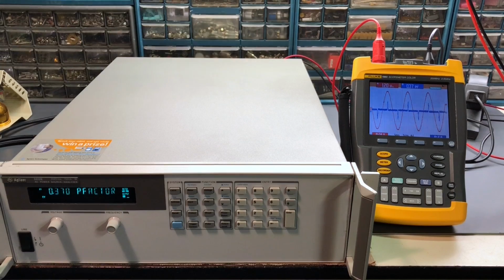So if I come up here, and I have to reach around the camera a little bit here, I'm going to increase the load on the power supply. So it's outputting just 1 amp right now, and you can see how those peaks are much larger now on the current waveform. The power factor has improved a little bit, 0.4, but still not that good.